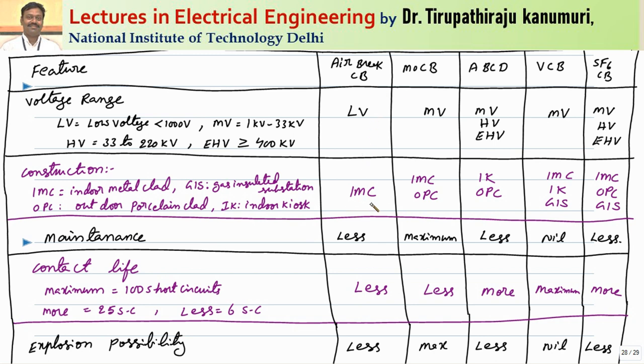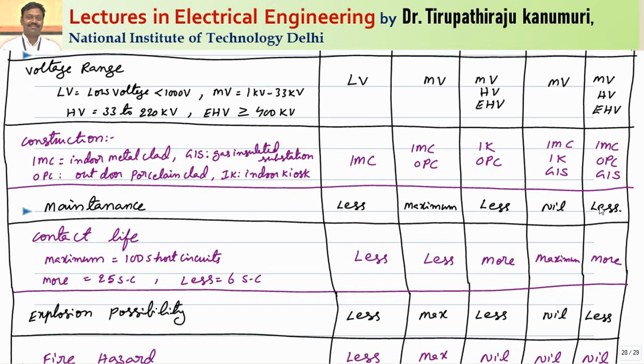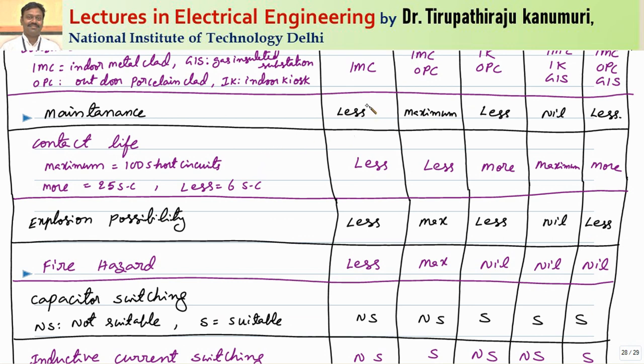Air brake circuit breakers are IMC type for indoor metal clad applications. Minimum oil circuit breakers can be used for either IMC or OPC type applications. Air blast circuit breakers are used for indoor kiosk or outdoor porcelain clad. Vacuum circuit breakers can be IMC, IK, or GIS. SF6 circuit breakers can be IMC, OPC, or GIS. For maintenance: air brake circuit breakers require very little maintenance since no oil or gas tank is needed. Oil circuit breakers require maximum maintenance — you must frequently test the oil, remove carbon deposits, and check the contacts.